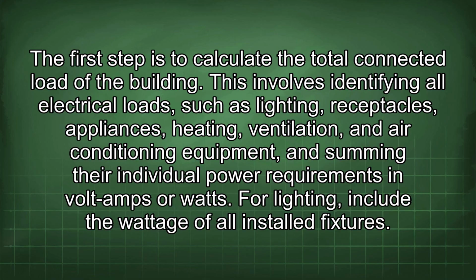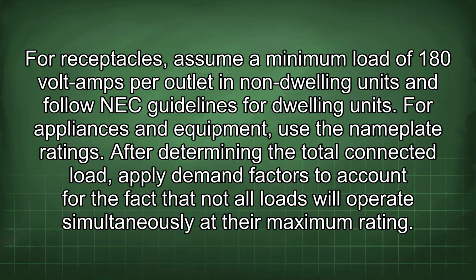For lighting, include the wattage of all installed fixtures. For receptacles, assume a minimum load of 180 volt amps per outlet in non-dwelling units and follow NEC guidelines for dwelling units. For appliances and equipment, use the nameplate ratings. After determining the total connected load, apply demand factors to account for the fact that not all loads will operate simultaneously at their maximum rating.